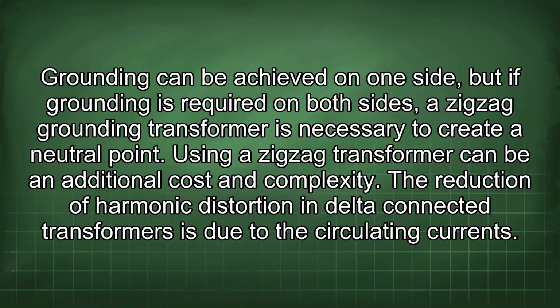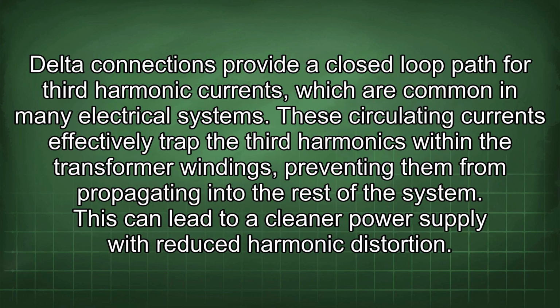The reduction of harmonic distortion in delta-connected transformers is due to the circulating currents. Delta connections provide a closed-loop path for third harmonic currents, which are common in many electrical systems. These circulating currents effectively trap the third harmonics within the transformer windings, preventing them from propagating into the rest of the system. This can lead to a cleaner power supply with reduced harmonic distortion.